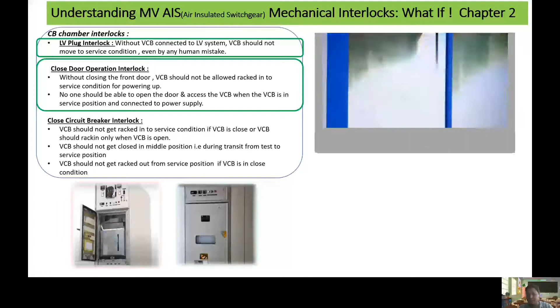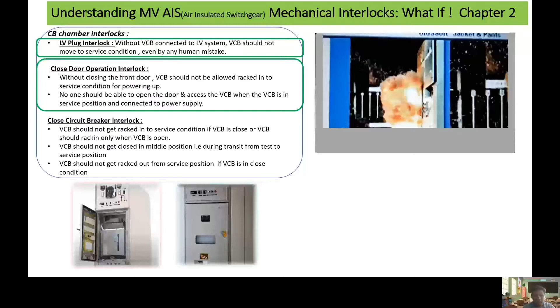So the door is open and the breaker is racked out from service to test position, and at the same time there is an internal arc which has happened due to short circuit, and there is an arc which is traveling out of the cubicle and hitting the person who was operating the circuit breaker. So this will happen if we don't have this interlock.